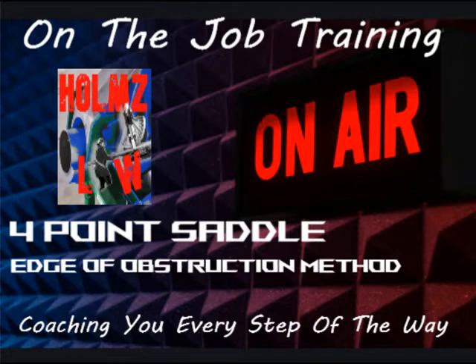Okay, and you're going to measure the width of the obstruction value. Okay, and you're going to be measuring that away from marks B and A. So you're measuring opposite away from those two marks that you just placed. And you're going to mark that down as the letter C. Make sure you make these marks all the way around the conduit, because we're going to be rotating this conduit, and you don't want to not have the mark in your sight.